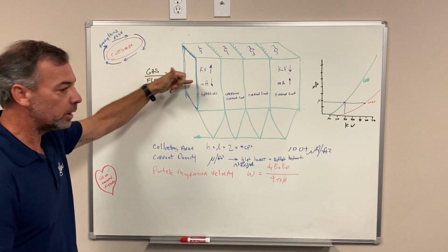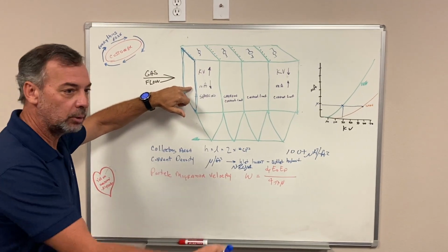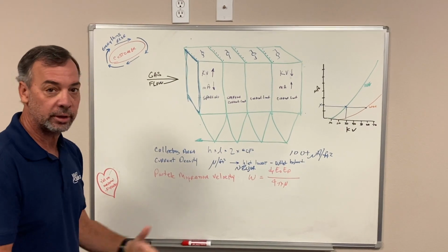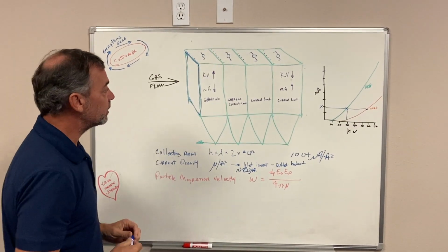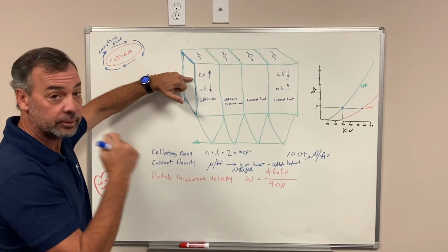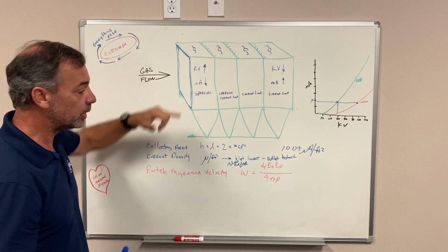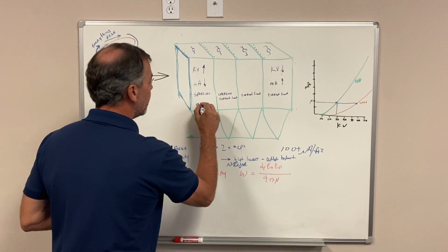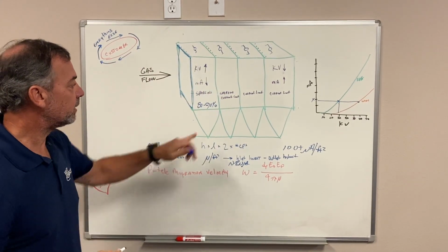You have low current. A lot of people interpret low current means, oh, low load. Like a motor, if it draws less current, it's not turning as fast or doesn't have as much torque to it. On a precipitator, it's different. Your voltage is the highest. So you have the most amount of force because there's so much particulate in that field, you're not getting a lot of electron flow. But you'll still collect 80 to 90% as far as mass weight of particulate on your inlet fields.